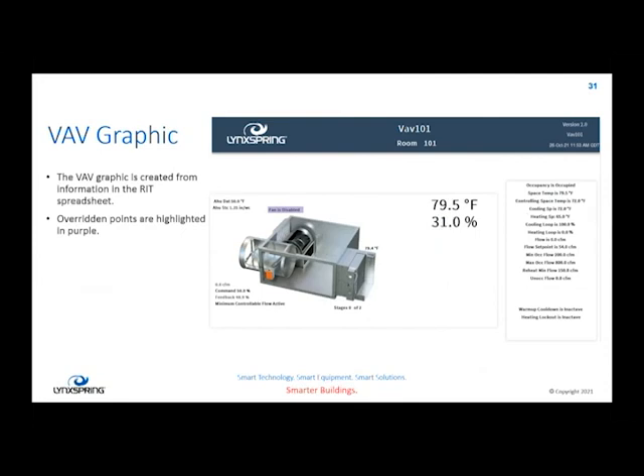We automatically build the graphic based off of the information that you put into that spreadsheet. That graphic, the exact same graphic, resides inside the VAV controller itself and at the supervisor, so it's in both places. So if your supervisor is not available when you have to start balancing and commissioning your VAV boxes, you can go in and use the exact same graphic at the VAV level. If your network is up, you can use a wireless, or whatever your building owner will allow you to do, so that your balancer or your tech can use a wireless network to go in there and connect to your VAVs. We also can plug directly into the VAVs with a USB mini, so that you can connect. So we have multiple ways to connect to those controllers.